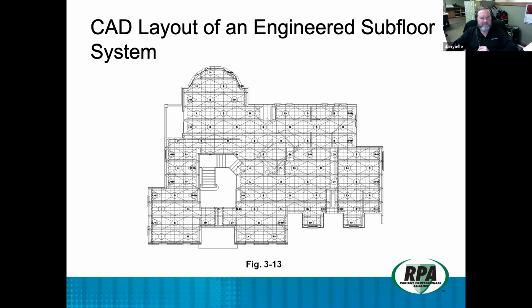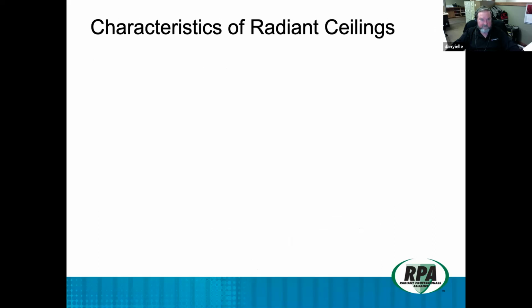They all go, "Ooh, that's expensive. What's the alternative? I haven't heard about gypcrete." Well, what they don't tell you about gypcrete is that you need 2 sole plates. You're going to have 15 pounds per square foot additional dead load that you have to handle, which means a deeper floor joist. It also means a lesser span between the support structures itself. So there's a lot of things that go into using gypcrete that don't just hit you in the face as being an additional cost. So when you take that into consideration, the gypcrete's really not all that much cheaper than the engineered flooring systems, and the engineered flooring systems work significantly better with lower water temperature of approach.